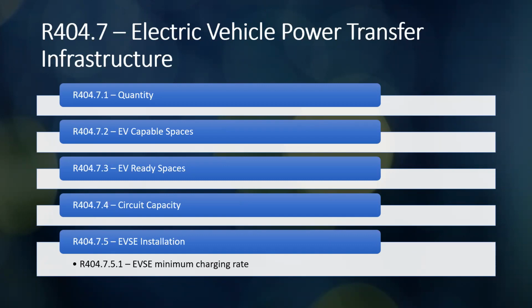So it says for exemptions, though, it says where the local electrical distribution entity has certified in writing that it is not able to provide 100% of the necessary distribution capacity within 2 years after the estimated date. So it's going to be, again, more specific on what is exempt and what's not. It's going to be something you'll have to talk to your building official on whether or not you're exempt with that part of it. And then circuit capacity management, it just says the capacity of each branch circuit serving multiple EVSE spaces, EV ready spaces, or EV capable spaces needs to be controlled by an energy management system providing load management in accordance to also that NFPA 70, and then shall have a capacity of not less than at least 2.7 kVA per space.